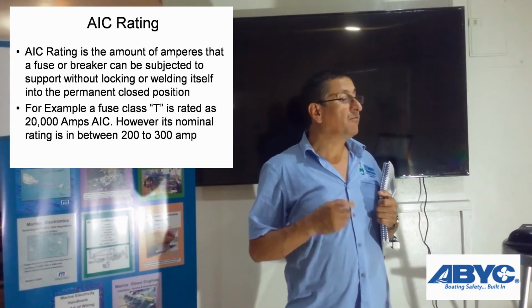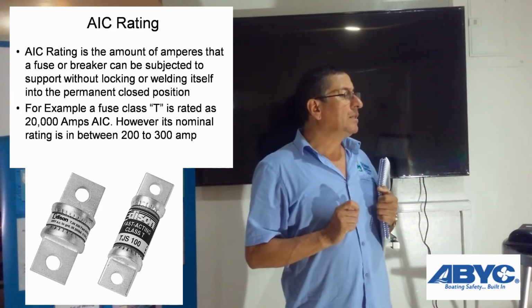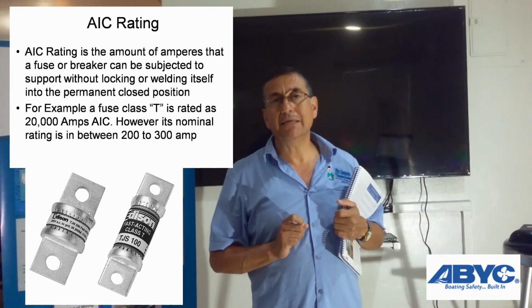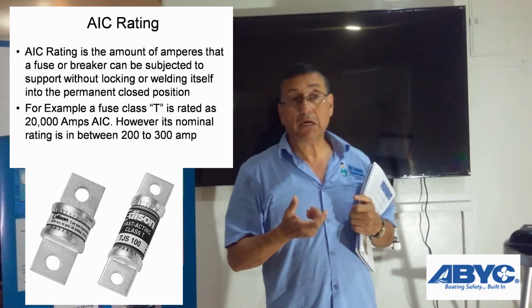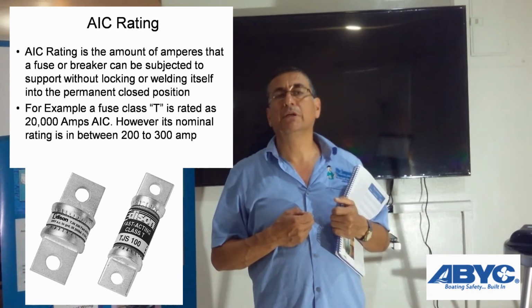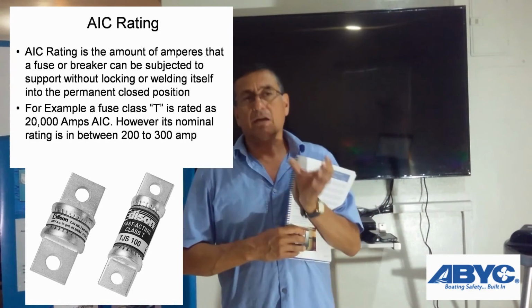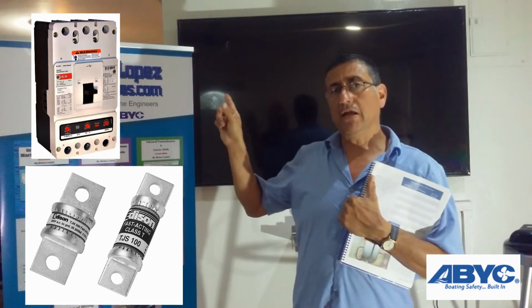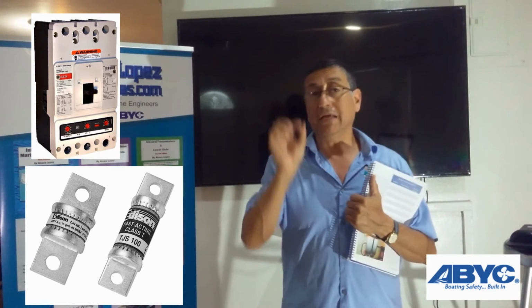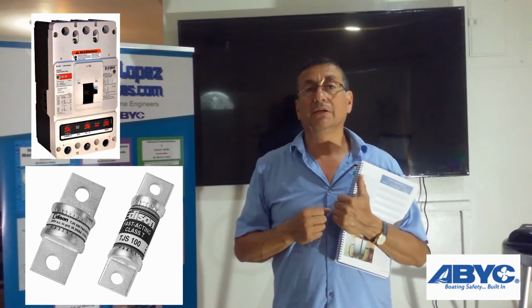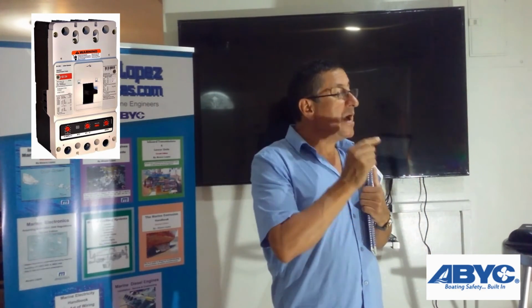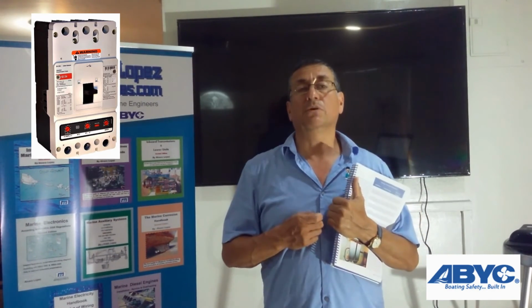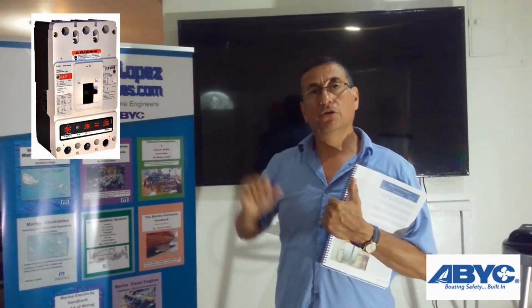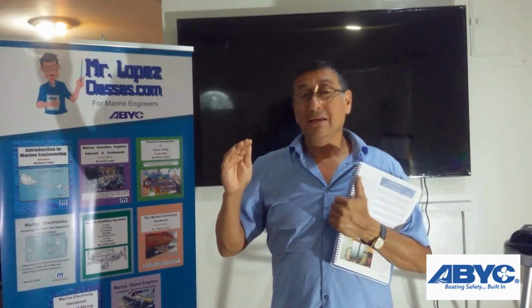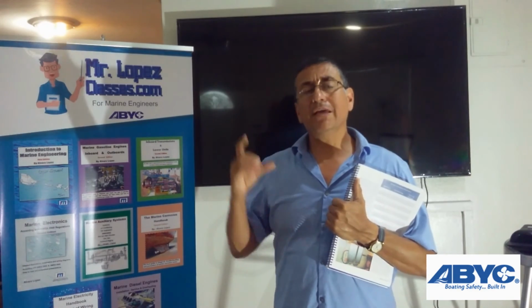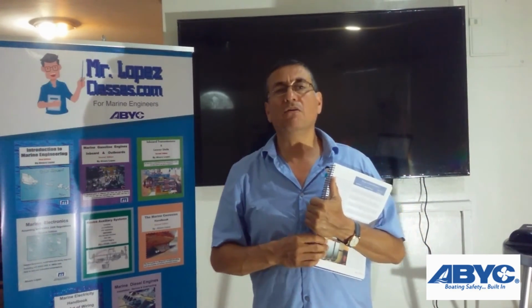ABYC has an example. ABYC says, for example, a class T fuse is rated with a 20,000 amps AIC. However, the nominal rating for that fuse is between 200 and 300 amps. In general terms, what is the meaning of that? Any breaker, for example, like the breaker that we have right now on the screen, for 200 amps. That's the number on the handle of the breaker, 200 amps. Internally, the AIC rating of that breaker is 20,000 amps. What is the meaning of that? If that breaker has the contacts closed, it can support up to 20,000 amps before the contacts are welded internally. This is the meaning of AIC.